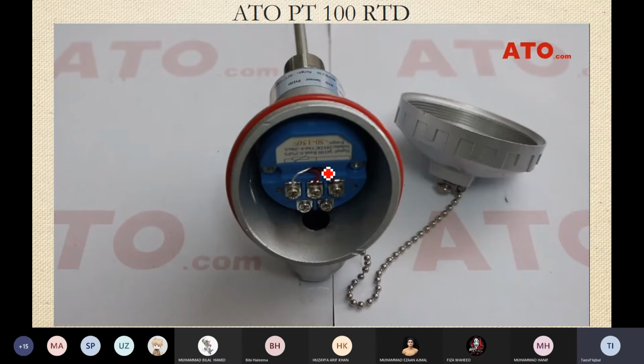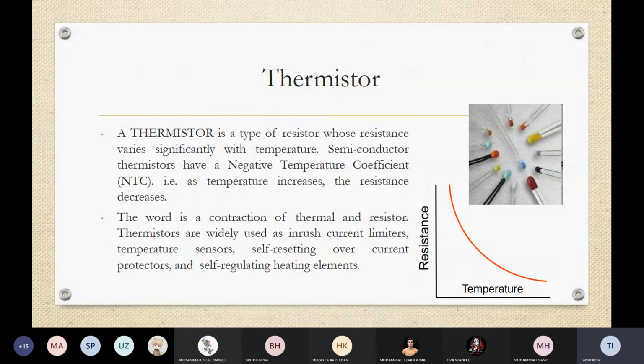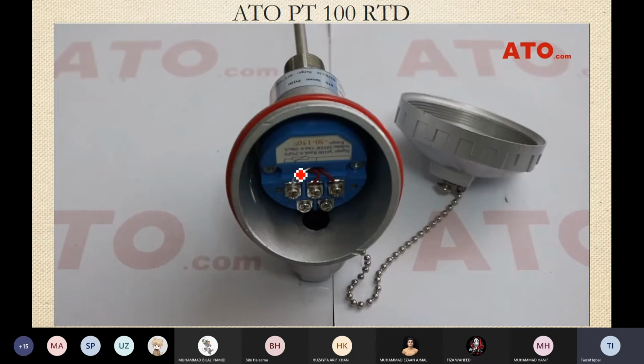And because this RTD is going to be placed in an industrial environment where there could be fumes, flammable fumes or gases, the head should be secure enough, or airtight enough, that no gas or fume goes into the electrical connection. So the safety concern is very important, and depending upon that safety concern, we have to design the transducer, the housing of that transducer, in such a way that it is not a risk for the environment, for the industry.